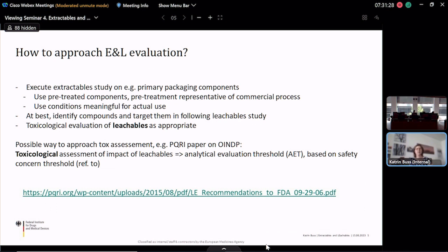So how to approach exactly an extractable leachable evaluation. The first step is the execution of an extractable study on, for example, the primary packaging component, and what has to be considered for that. As Claudia already mentioned, the components should be pre-treated according to the intended pretreatment for the commercial process. For example, if you want to investigate a rubber stopper, that is usually pre-sterilized or can be pre-sterilized, and then depending on what method is used for sterilization, irradiation or steam sterilization, the component should be pre-treated accordingly. And also the other use conditions which are meaningful for the actual use.